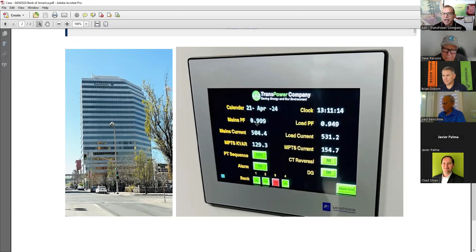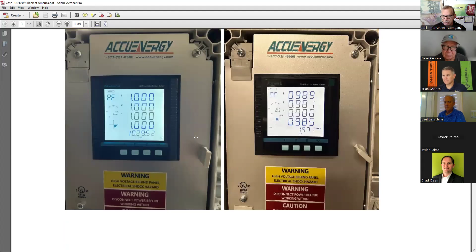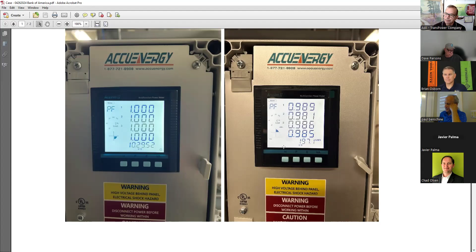You see, on a Sunday afternoon there's hardly any load, and it was running at 94.9% power factor, and it took it to 0.999. Here is the verification on the MPTS - you get two sets of data matching up, and the third set is the utility meter. That's how you verify billing errors - that's the third element of the MPTS.